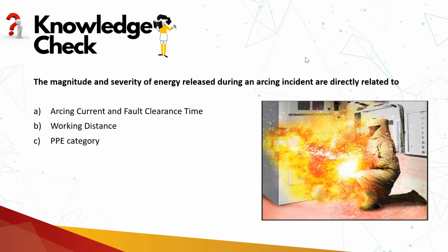The magnitude and severity of energy released during an arcing incident are directly related to arcing current and the fault clearance time. So the question is asking about the magnitude and severity of energy release. It's not talking about the incident energy. So energy released will be based on A, arcing current and fault clearance time.